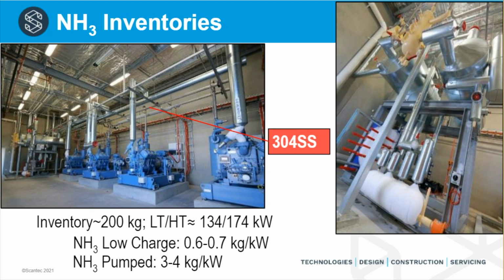Again, this is a refrigerated warehouse that is approximately 40,000 cubic meters in volume, and again, it's a food service business. What you can see in the background behind the compressors is the vessel unit, and on the right-hand side in the picture, you can see a more detailed picture of the vessel unit with the plate heat exchanger. That's the blue thing there, below the intercooler and the low temperature separator. And the frosted up thing in the foreground is the oil drain vessel that takes the oil out of the two vessels you can see above.